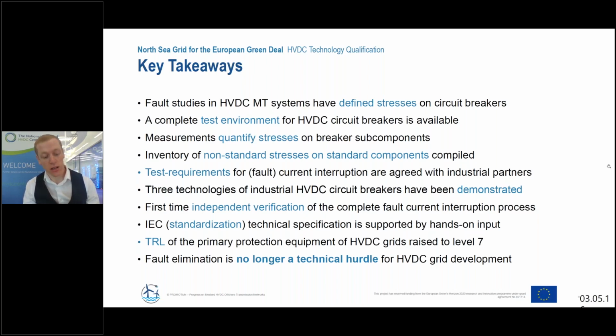An interesting question directed at the breaker technology verification was, harking back to the use of models, what are the limits of these models? And you could alternatively view this question as, why are physical tests required? And the answer coming back highlighted that there's stochastic variables to consider, which field measurements can perform. And it also pointed out that models developed are mostly looking at the electrical parameters, but there's still a large mechanical aspect to consider, and that's where these physical tests really come into their own.